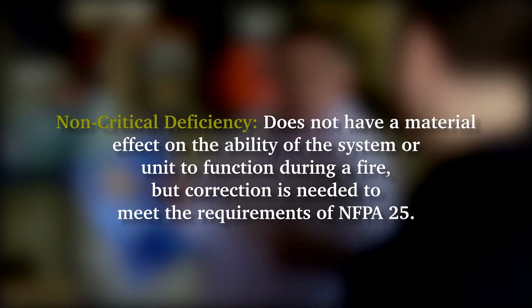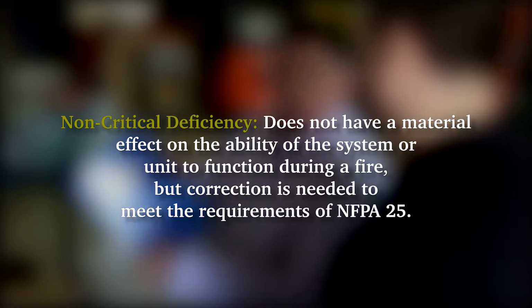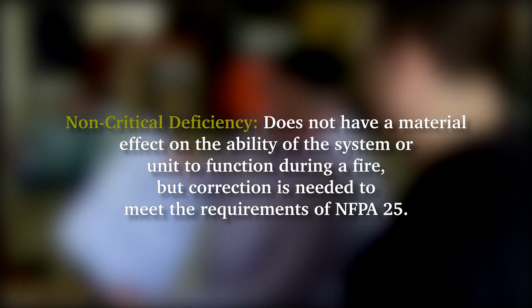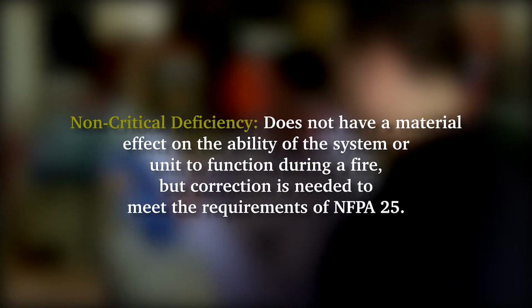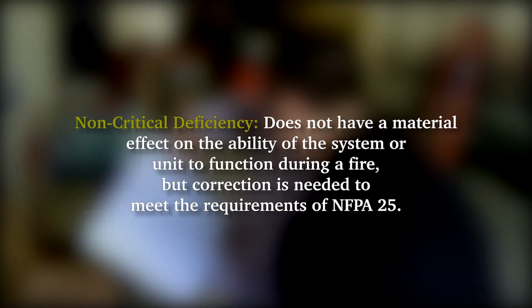A non-critical deficiency does not have a material effect on the ability of the system or unit to function during a fire, but correction is needed to meet the requirements of NFPA 25. An example of a non-critical deficiency would be incomplete testing documentation or missing tests for a building.